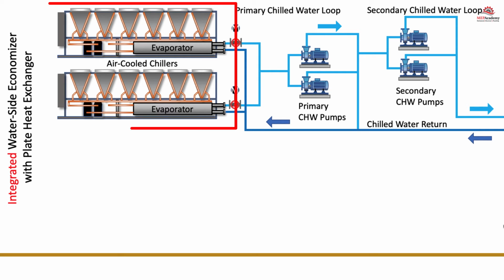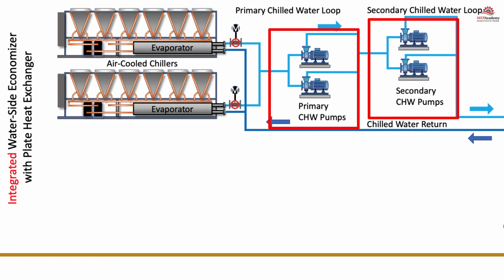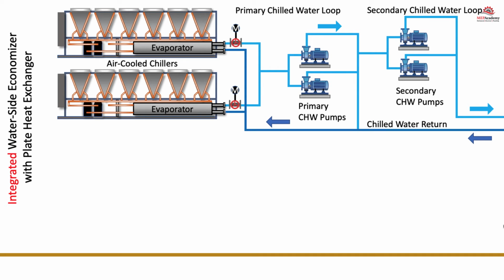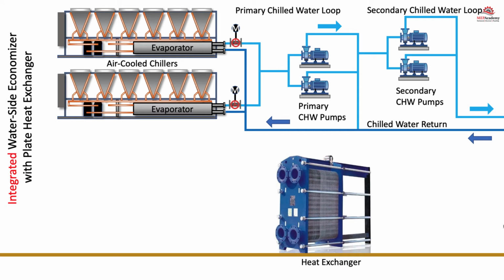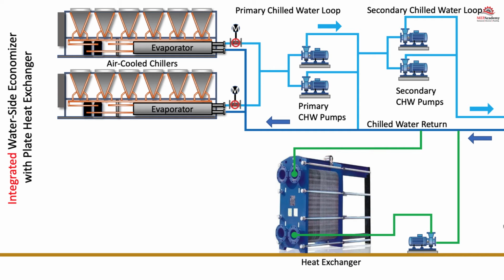Here we have two air-cooled chillers with primary pumps and variable secondary pumps serving the building load. We can pre-cool the returning chilled water temperature before it enters the chiller, thereby taking load off the chiller. We add a plate and frame heat exchanger to the system and a pump which will pull water out of the chilled water return and send it through the heat exchanger, where it will give up some of its heat and be sent back into the chilled water return on its way to the air-cooled chillers.